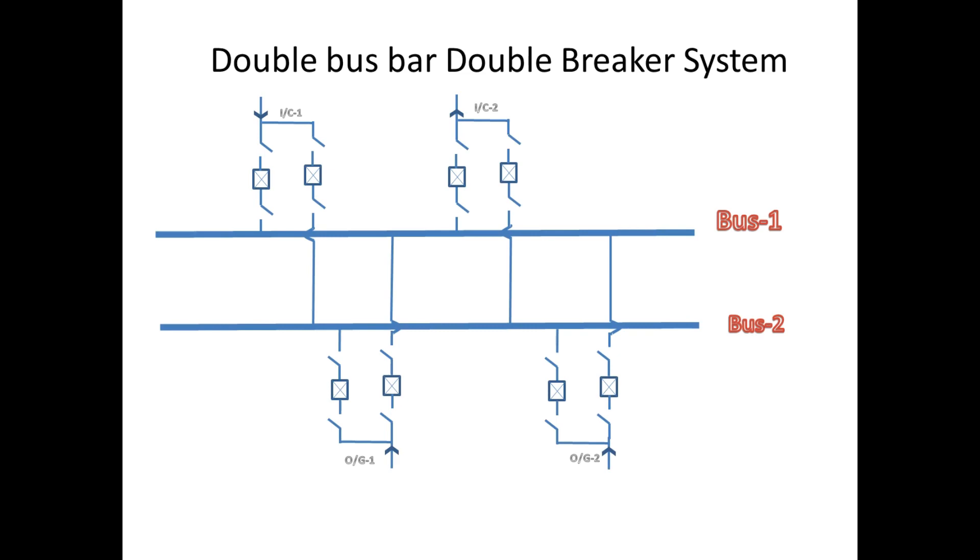Similarly, when de-energizing, first the breaker has to open, then the corresponding isolators have to be opened. This type of bus bar arrangement is mostly used in 400 kV substations.